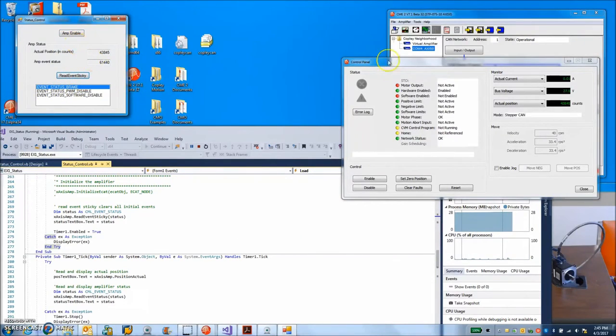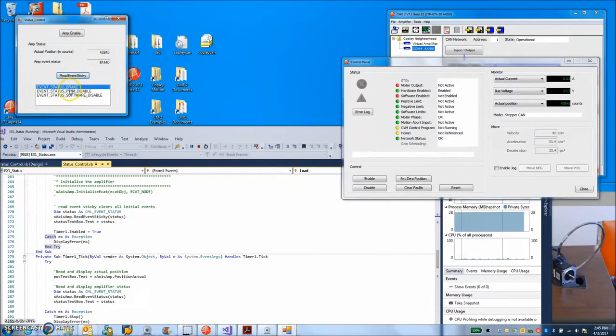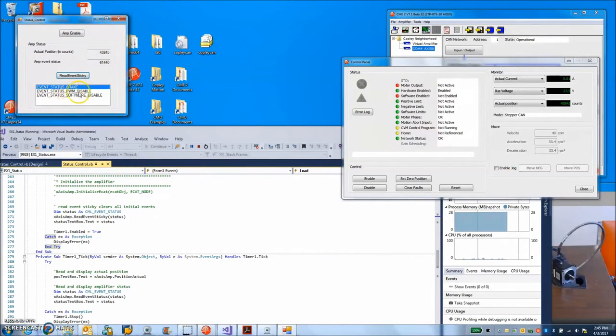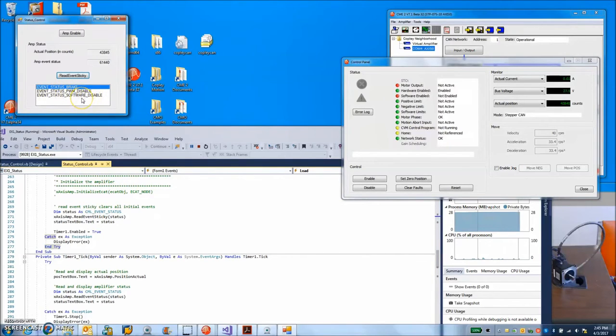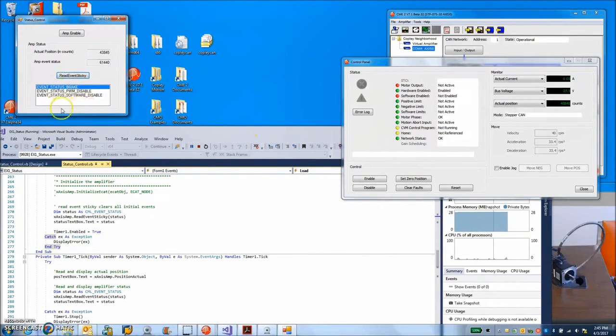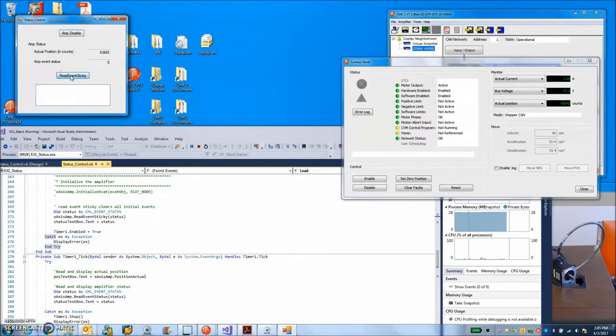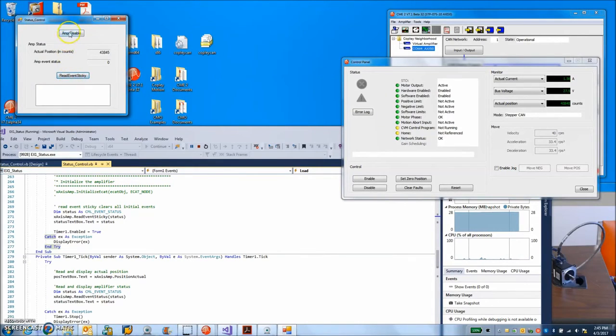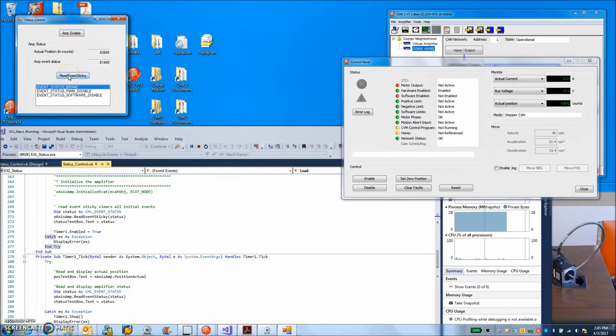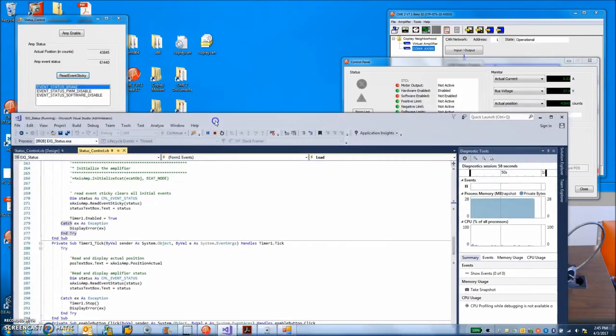I'm reading the event status sticky. I got a brake turned on. I got PWM outputs disabled and I'm software disabled. So if I had a fault, you know, you can see that too. So as a sticky event, as you read it, it disappears. So that's how we can check out the status of the drive.